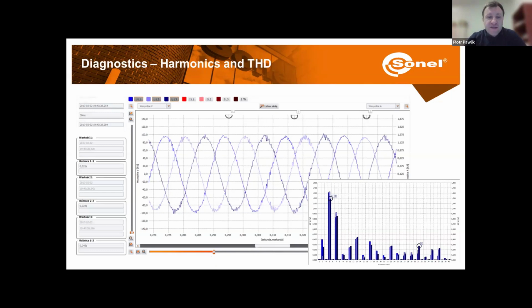If the harmonics in a power system exceed the limit set in the regulation, it may be necessary to disconnect the problematic charger, which will certainly cause frustration to the users. But we need to remember that the presence of voltage and current harmonics is a natural consequence of commonly used electronic devices. So it is worth checking their level even before installing the charging station. And in case of high harmonics content in the voltage, it may turn out that after connecting the chargers, the limit may be exceeded. Even if not, a higher harmonics level can cause various negative effects in the mains, such as overloading the neutral line, poorer performance of devices, vibrations, or difficult starting of the motors connected to the mains.